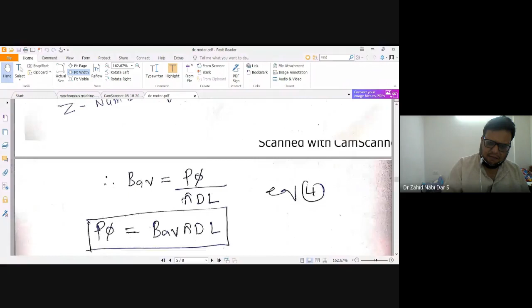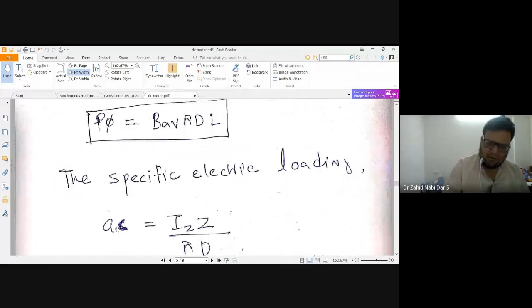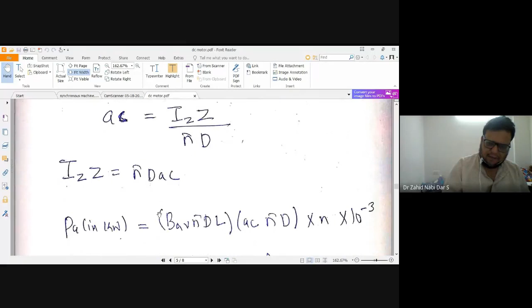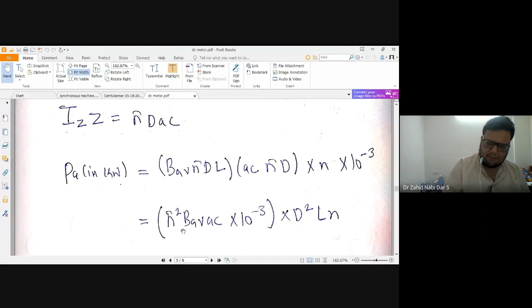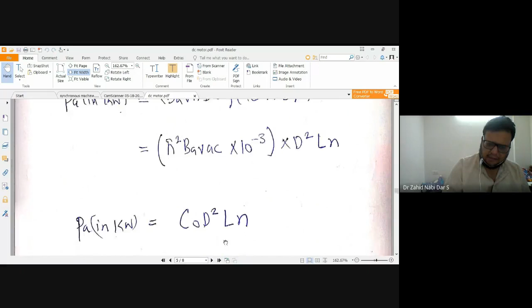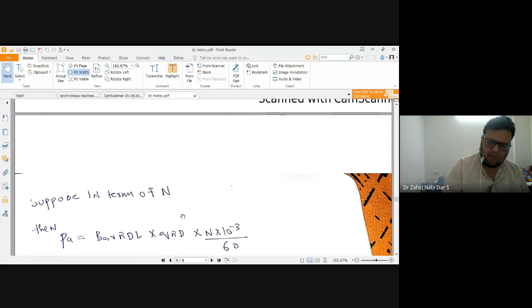So in my complete equation, I see one term is P phi. This term P phi I can express in terms of magnetic flux density. Then I have another term Ia by A that I can express as Iz into Z, and the rest is 10 power minus 3 into n. So Iz into Z I can express in terms of ampere conductors, and P phi will be BAV pi dl, and the specific electrical loading Iz into Z in terms of AC I can express as pi d AC. So with this, BAV, and n in 10 power minus 3, I get an output equation: pi square BAV AC in 10 power minus 3 into d square ln. In kilowatts, I can write C naught d square ln, and I can resubstitute here if I want in terms of capital N.